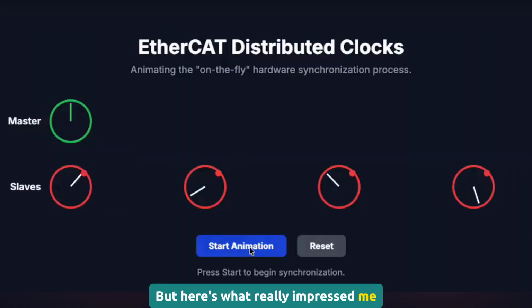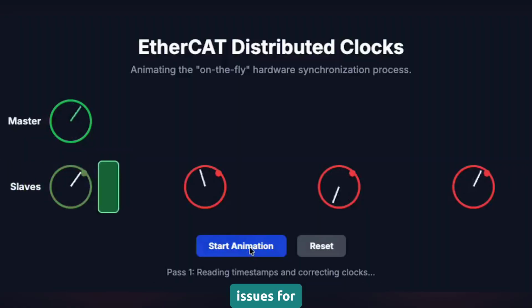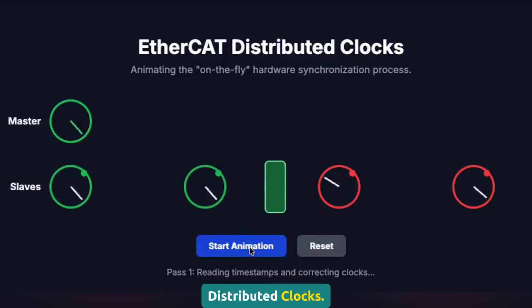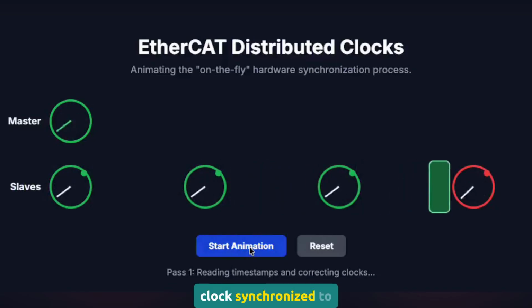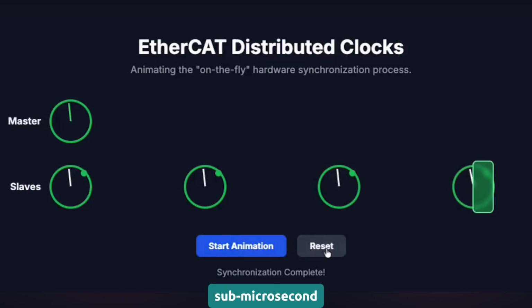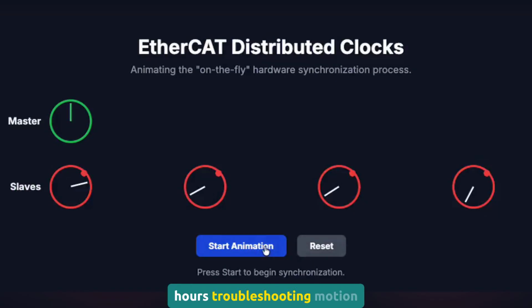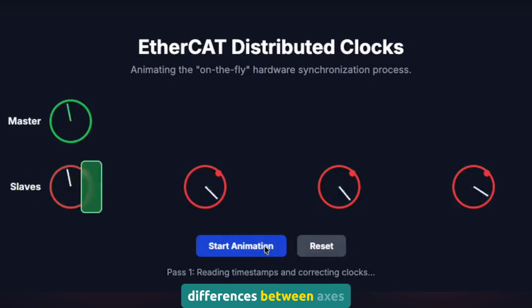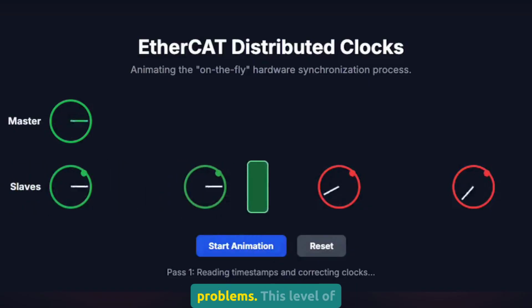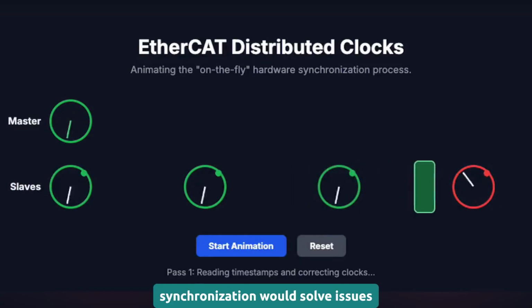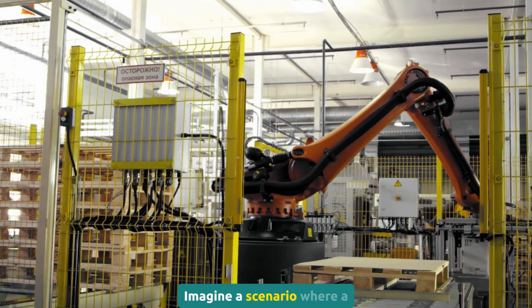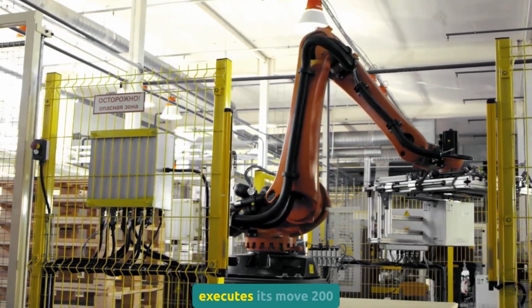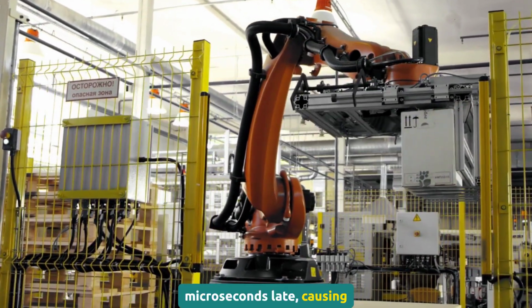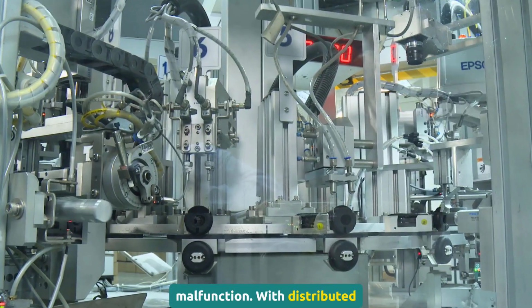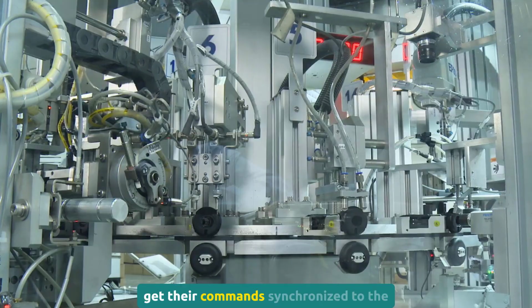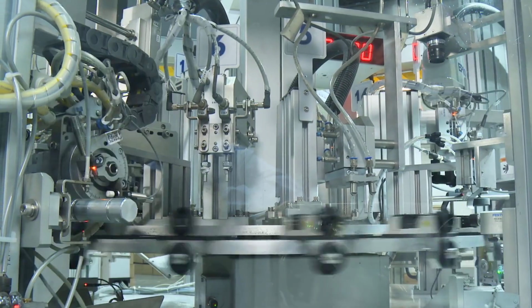But here's what really impressed me as someone who's fought jitter issues for decades. EtherCAT's distributed clocks. Every device gets a hardware clock synchronized to sub-microsecond precision. I've spent countless hours troubleshooting motion systems where slight timing differences between axes cause coordination problems. This level of synchronization would solve issues I experience regularly. Imagine a scenario where a 20-axis packaging machine executes its move 200 microseconds late, causing the entire sequence to malfunction. With distributed clocks, all axes get their commands synchronized to the same hardware time base.